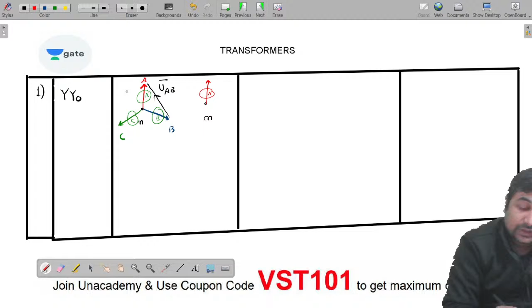Again taking the same neutral as reference, always remember induced EMFs are in the same phase, so draw a line parallel to A phase. This line is parallel to A phase only when this terminal is A2 and this terminal is A1. For that, keep in mind that for the HV side, A phase is brought out from terminal A2.